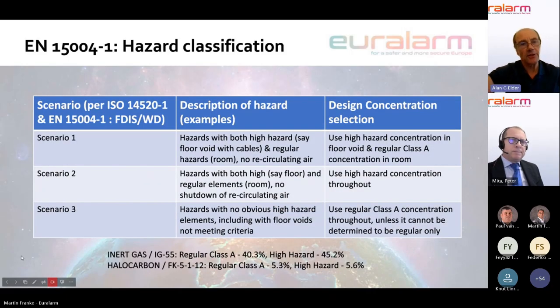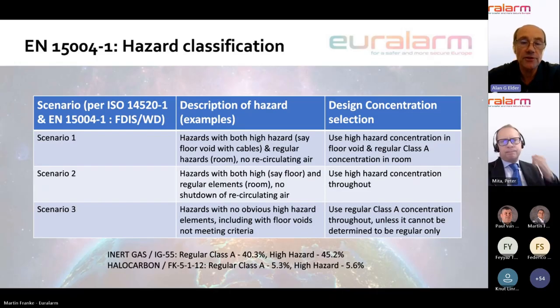And so in this slide, we've identified 3 fairly common scenarios that would exist. So scenario 1, this is where hazards with both a high hazard, say floor voids with cables, and regular hazards, for example, the room, with no recirculating air present. What you would do in that situation is you would use the high hazard concentration in the subfloor and a regular Class A concentration in the room.